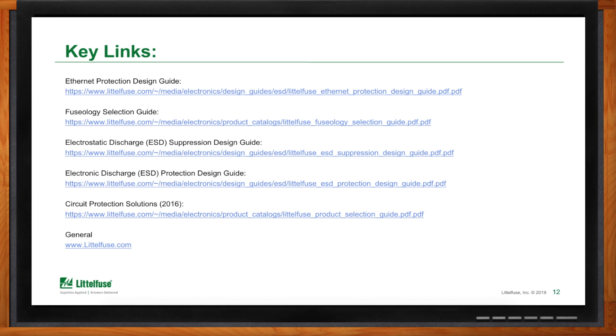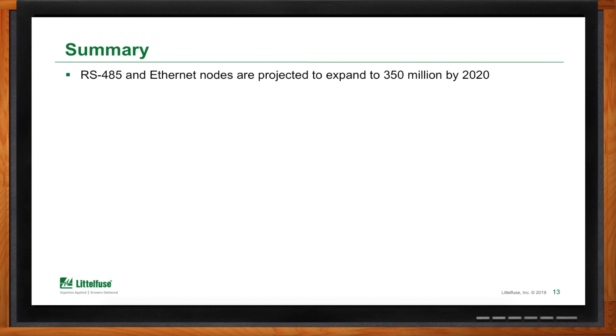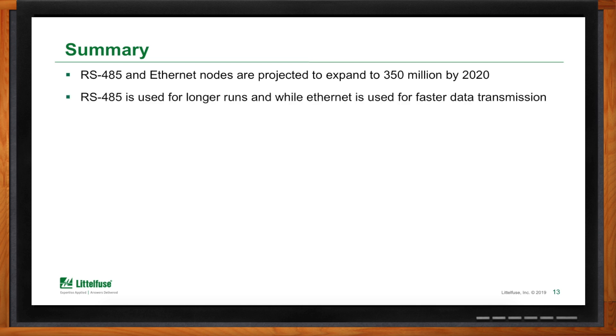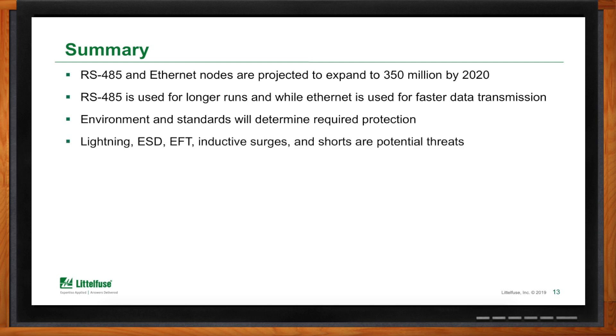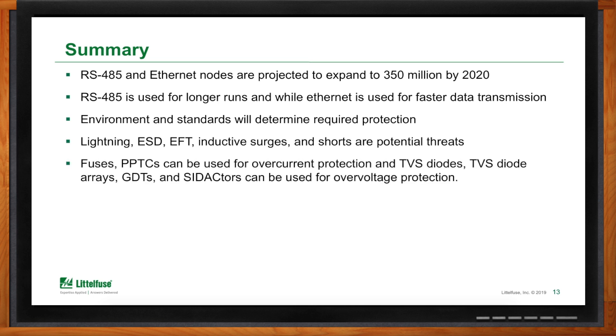To summarize: by 2020 we'll have over 350 million nodes for RS-485 and Ethernet. RS-485 is typically used for longer runs such as remote I/O, while Ethernet is used when you need more data speed, such as for security cameras or imaging systems. Your external and internal environment will impact your protection needs, as will applicable standards. Lightning, electrostatic discharge, electrical fast transients, inductive surges, and shorts all impact protection needs. Fuses and PPTCs are used for overcurrent protection, while TVS diodes, TVS diode arrays, GDTs, and SIDACtors are used for overvoltage protection.